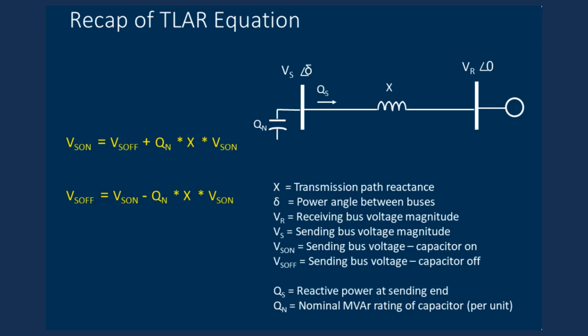So if we are switching a capacitor in service, then the voltage with the capacitor on is the voltage with the capacitor off plus the nominal megavars of the capacitor bank times the reactance between the buses, and we also multiply it by the voltage with the capacitor on.